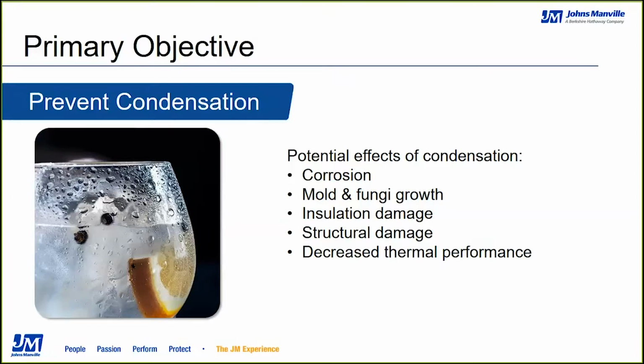You can damage your insulation systems, or you can create structural damage. Like Sean mentioned earlier in her presentation, a system that is sweating could cause damage to ceiling tiles or other building products around the system. And regardless of whether the system is fiberglass or some alternative material, in a chilled water system that is getting condensation, we are decreasing the thermal performance of that system.